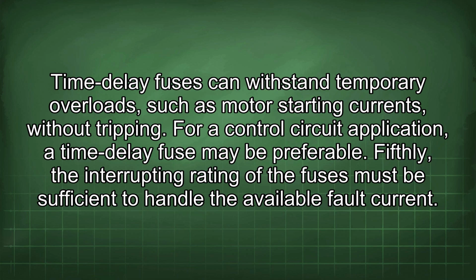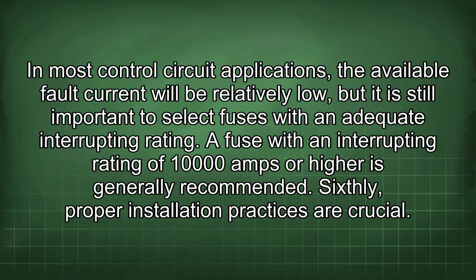Fifthly, the interrupting rating of the fuses must be sufficient to handle the available fault current. In most control circuit applications, the available fault current will be relatively low, but it is still important to select fuses with an adequate interrupting rating. A fuse with an interrupting rating of 10,000 amps or higher is generally recommended.